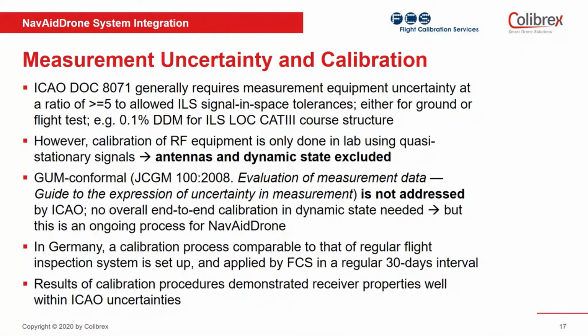So this short interval is a requirement in Germany, not worldwide, and it does definitely not mean that the short calibration is really needed for the receiver, which is a very stable device. But since we carried out many calibrations so far, we came to the conclusion that we are very well within the given ICAO uncertainties. And so we operate now 3 receivers, and all of them undergo this calibration interval and get a calibration certificate afterwards. And well, it looks like that we are very well within the ICAO uncertainties. Yeah, thank you. That's all from my side, and I will hand over back again to Luc.